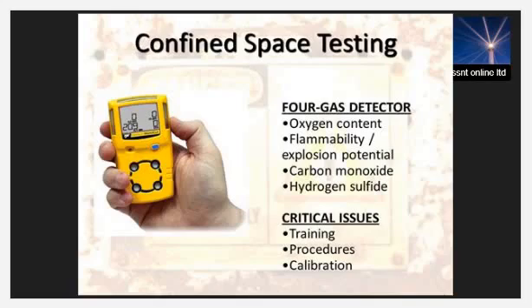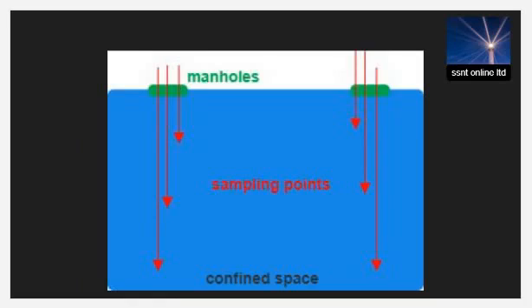Evaluation testing is done to determine what chemical hazards are or may become present in the space's atmosphere, and to identify what steps must be followed and what conditions must be met to ensure that atmospheric conditions are safe for a worker to enter. For confined spaces that are deep or have areas leading away from the entry point, the atmosphere may be layered or different in remote areas. For these spaces, testing must be done at different levels and in all available areas.